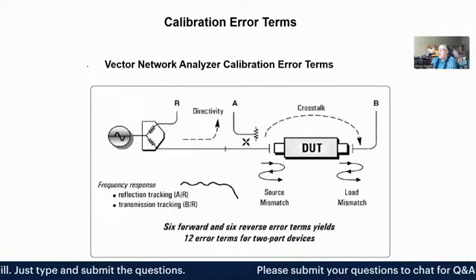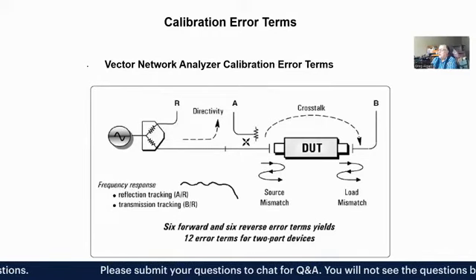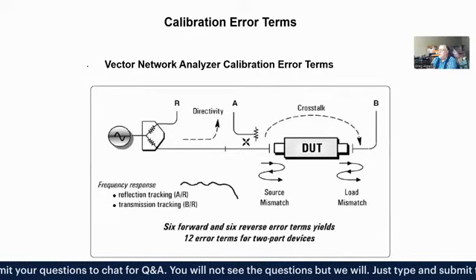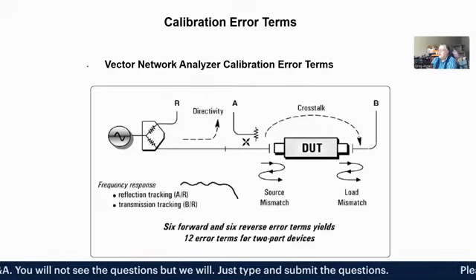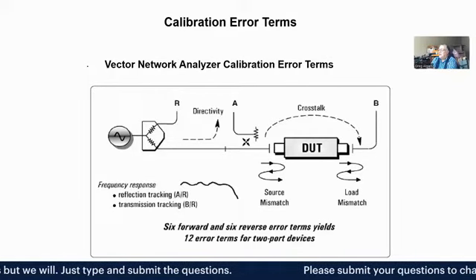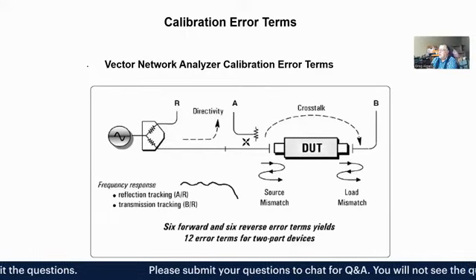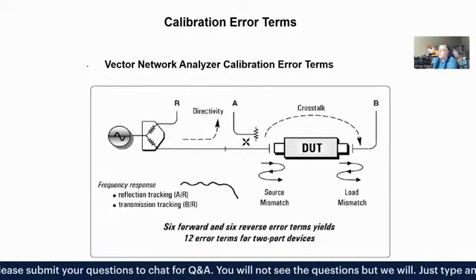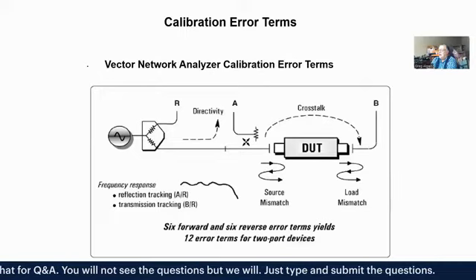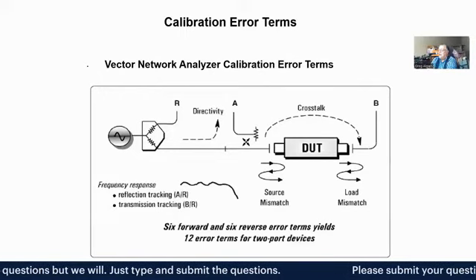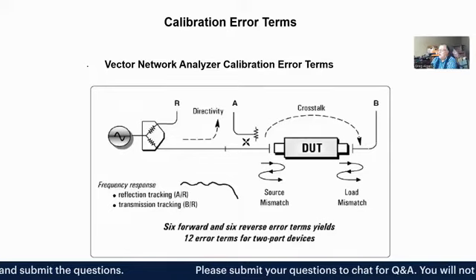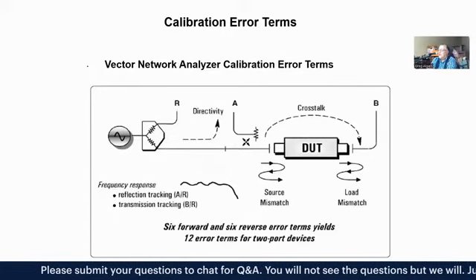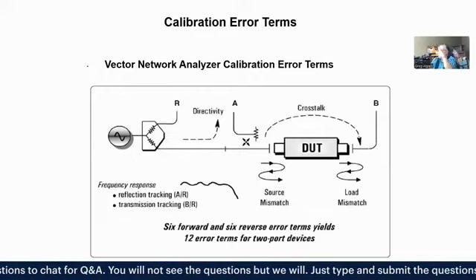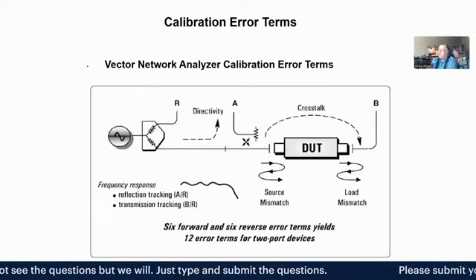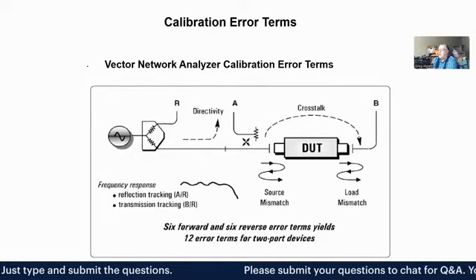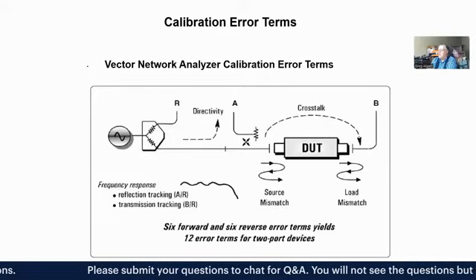Here are the errors that it actually looks at. This is called a 12-term error model. There's 6 forward and 6 reverse errors that it looks at. Things like source and load match errors, crosstalk between the input and output ports, directivity of the coupler, that's leakage that comes through the coupler, and the fact that when you measure an RF device over some frequency, the measurement varies with frequency a little bit, so you get what's called frequency response tracking errors that it takes out as well.